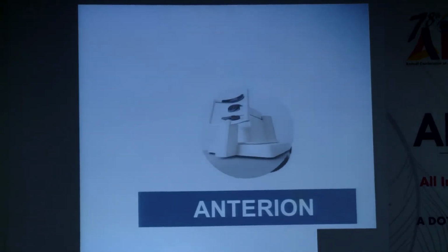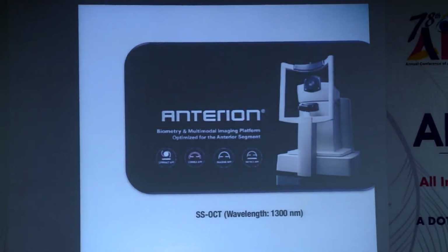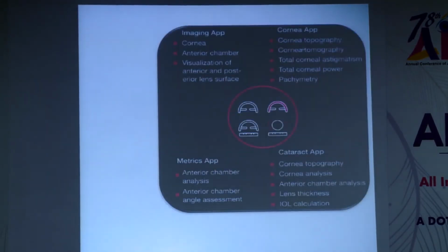So what Anterion does here is it combines all of this into one machine, into one place where the machine is kept, and the patient does not have to be moved from that spot. It is an all-in-one machine. So it works on the swept source OCT principle. It has a wavelength of 1300 nanometers.